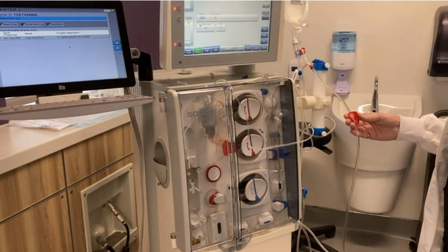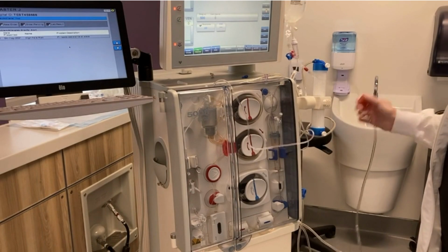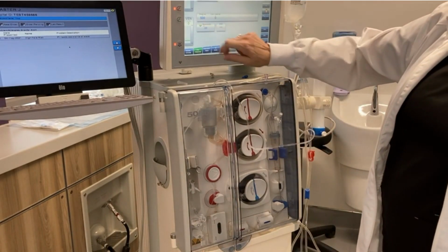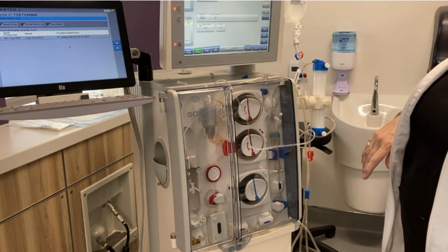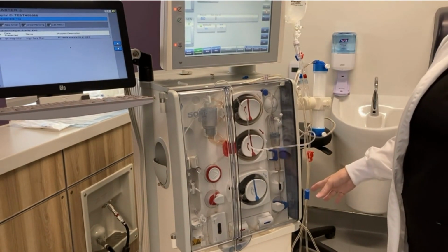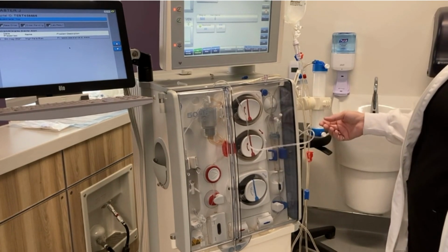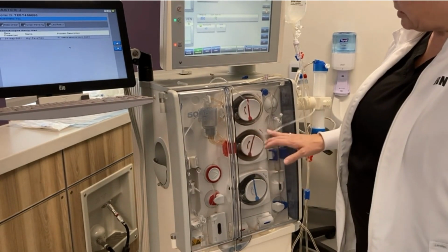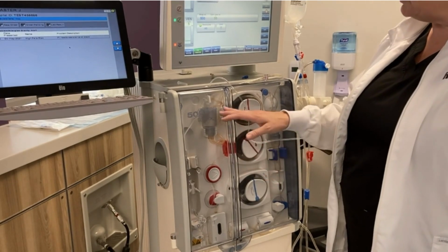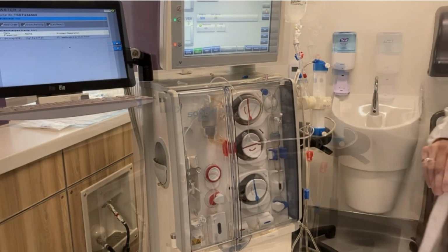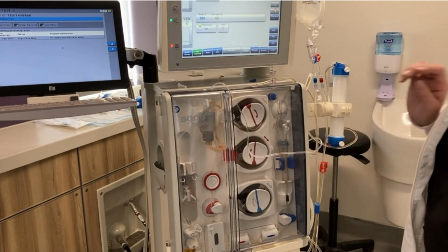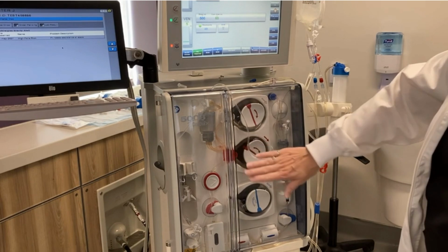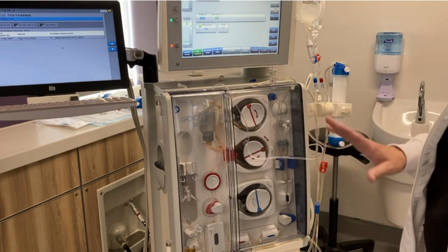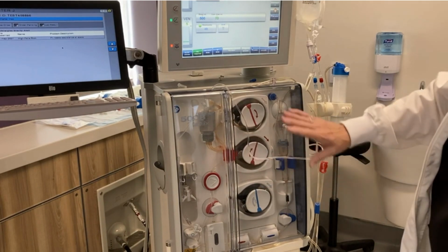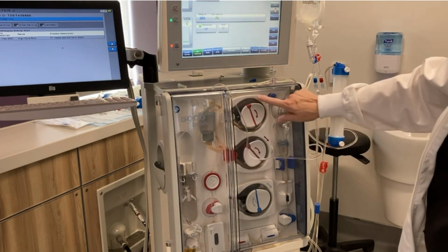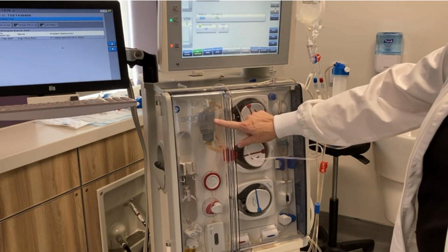Once the saline gets into your arterial line, clamp, and then you can go ahead and turn on your blood pump. And that is going to prime your lines, just as for your normal setup, through your arterial pump and into your arterial chamber. So your standard setup, we have just the one pump. So the only difference between the single needle setup and the standard setup is for the single needle, we have the second arterial pump and we have the arterial chamber.